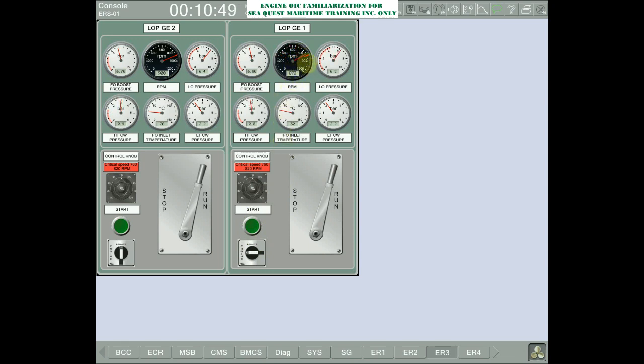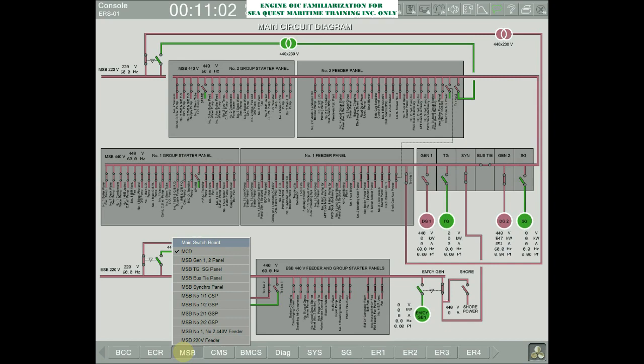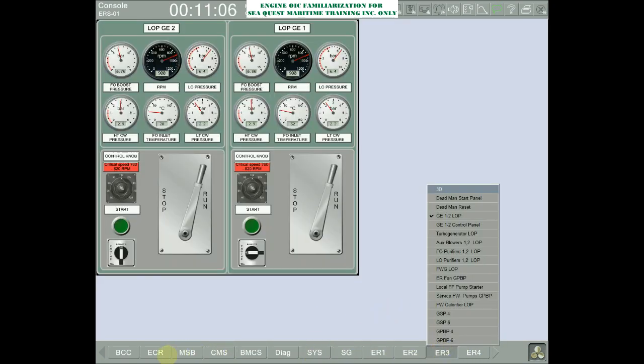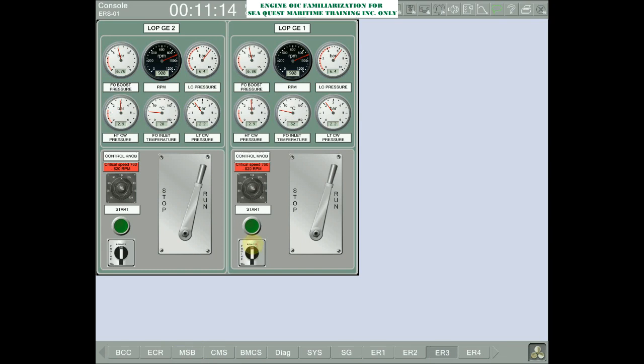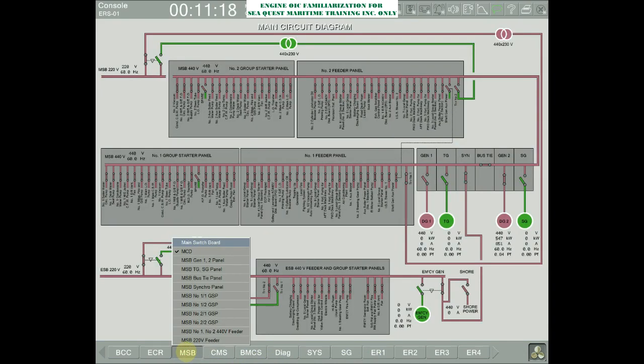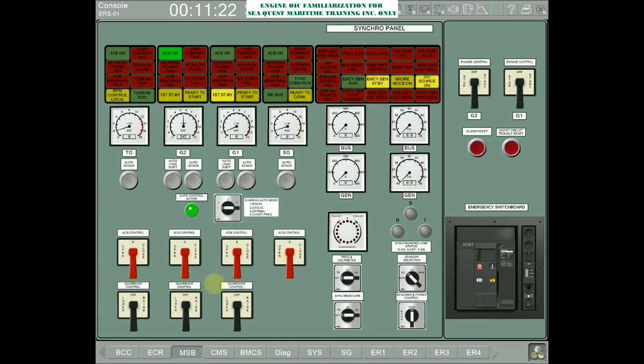Watch the RPM of the generator engine, and then as soon as it reaches 900 RPM, go to MSB. Oh, by the way, before we go to MSB, we have to put the LOP GE 1 to remote, otherwise it will not be synchronized. And then go back to MSB, select synchro panel, and then put selector knob of frequency and voltmeter and synchroscope to G2 or G1 because we are going to synchronize G1 or G2, whichever is going to be synchronized.